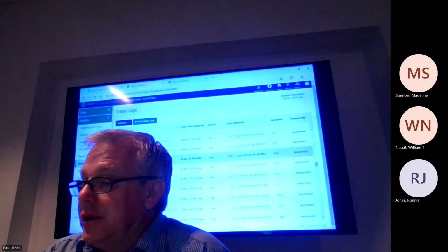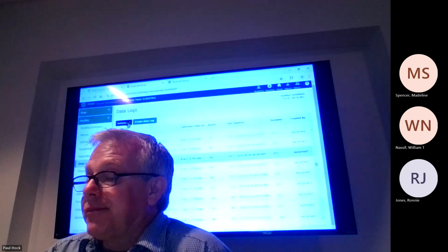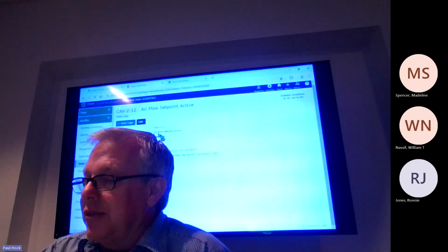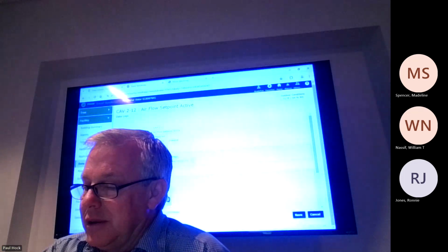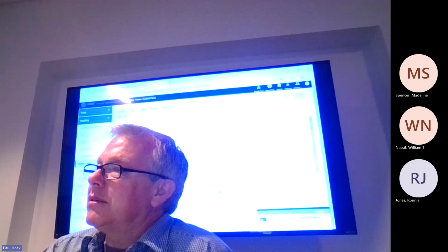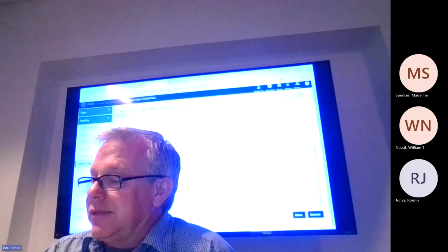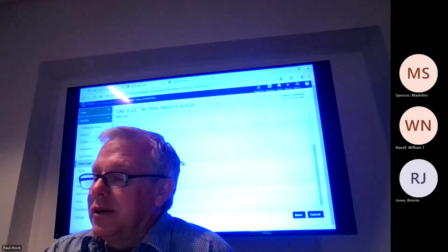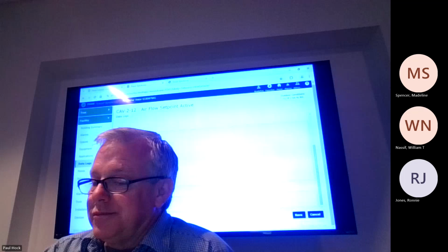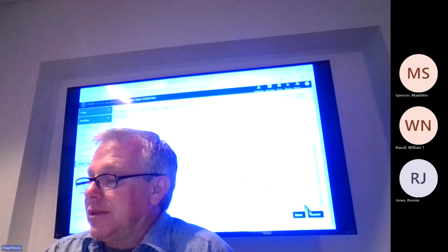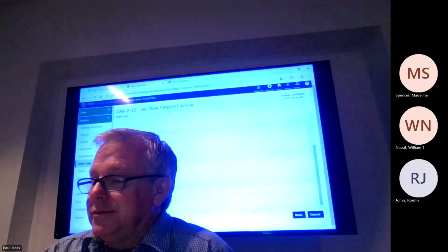If you need longer, you just click on the little box there. View data log. And like I said, you can play with this. Edit. I can do up to 3 years, I think. 200 and some thousand data logs is the limit. So it'll do a year's worth of data, looking at it every 15 minutes, or I can change that to 5 minutes or 1 minute. Maybe 6 months. Oh, too big, 125,000 samples. So I could probably go 3 months.